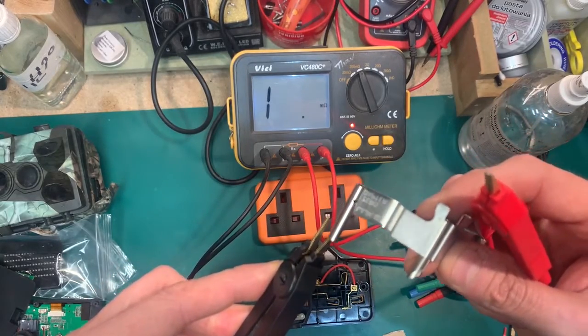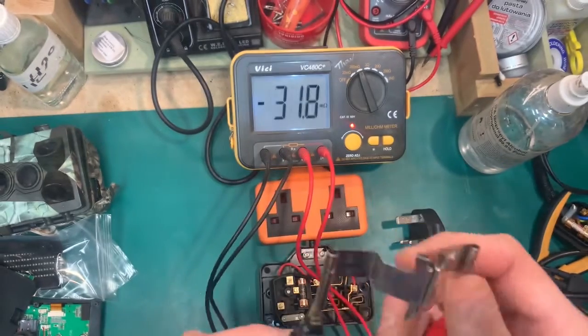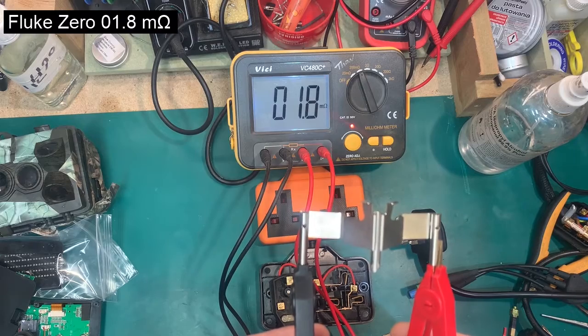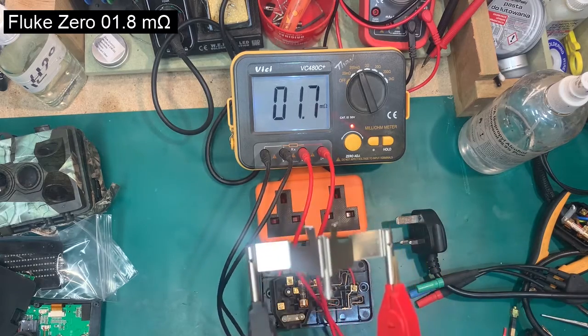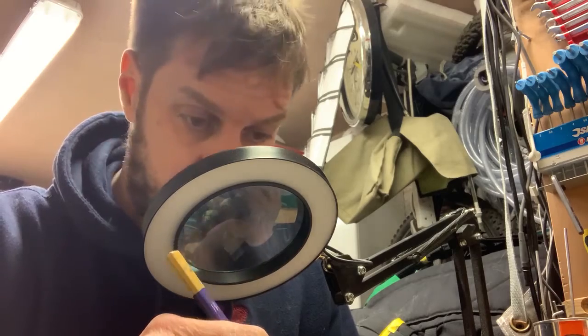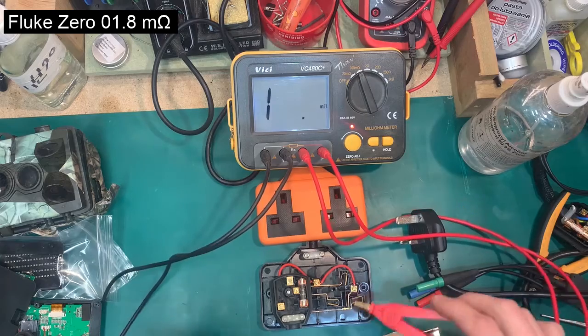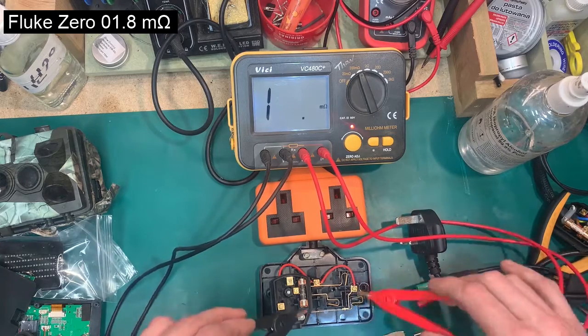I'm doing the measurement right on the end of these probe zeroing things on the Fluke zeroing device. Got a good contact, and that comes out at 1.8 milliohms — so 1.8 thousandths of an ohm — on the Fluke adapter.